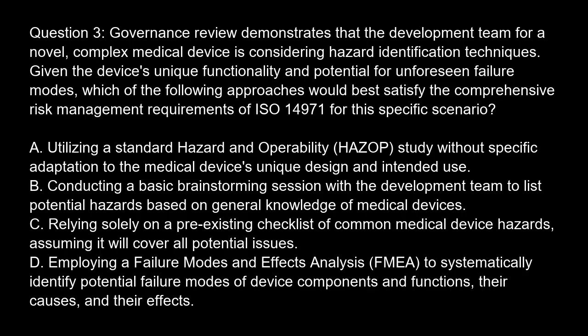Option A. Utilizing a standard hazard and operability (HAZOP) study without specific adaptation to the medical device's unique design and intended use. Option B. Conducting a basic brainstorming session with the development team to list potential hazards based on general knowledge of medical devices. Option C. Relying solely on a pre-existing checklist of common medical device hazards, assuming it will cover all potential issues. Option D. Employing a failure modes and effects analysis (FMEA) to systematically identify potential failure modes of device components and functions, their causes, and their effects.